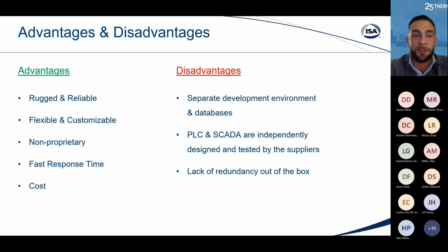Now for the disadvantages and ways to combat them. First, there are separate development environments and databases between the PLC and SCADA systems. This can lead to compatibility issues and increased risk for errors and mistakes. To combat this, allow for additional development time and a very robust factory acceptance testing phase to work out the kinks and bugs before you get to site.